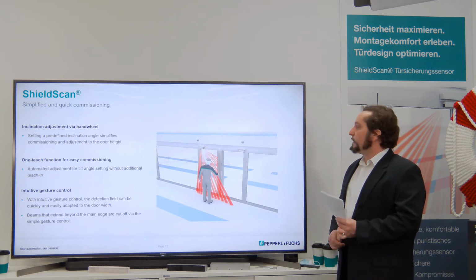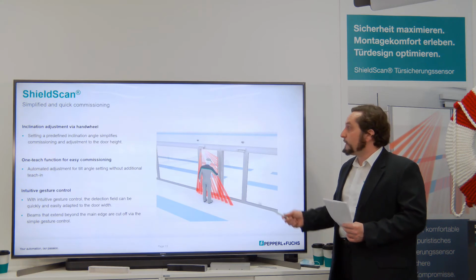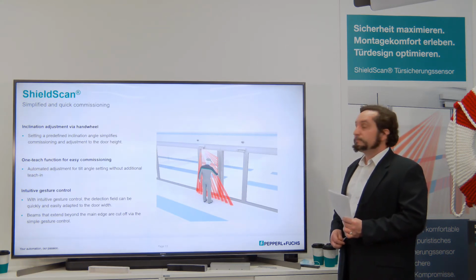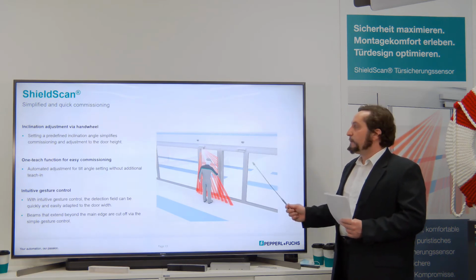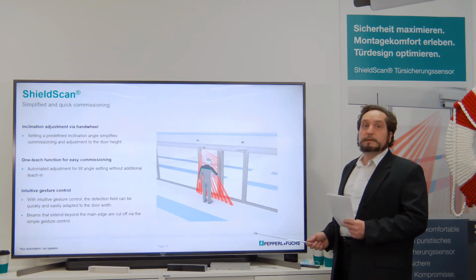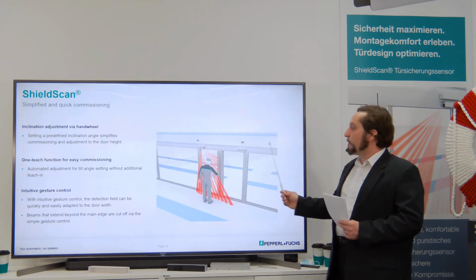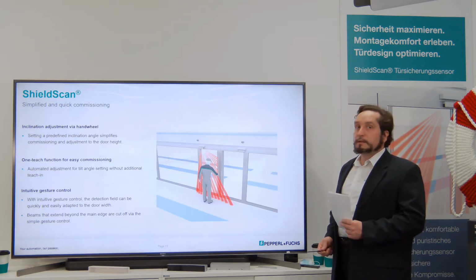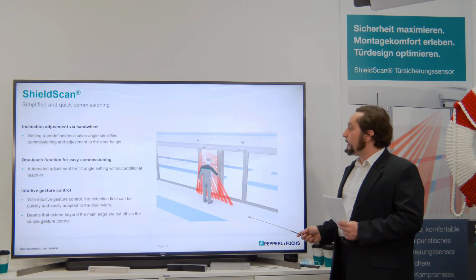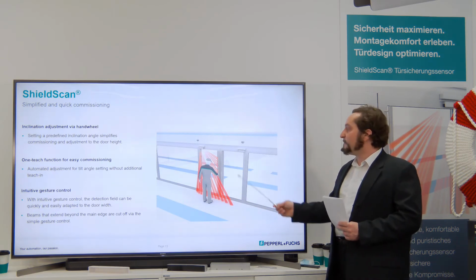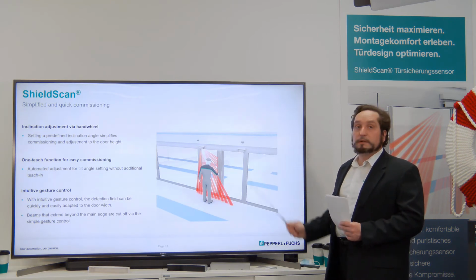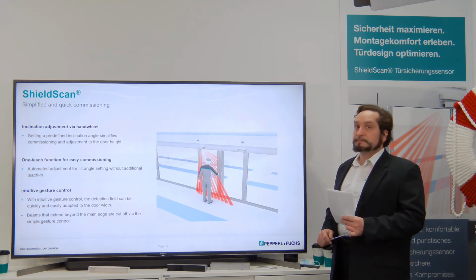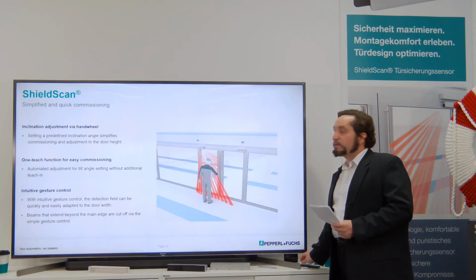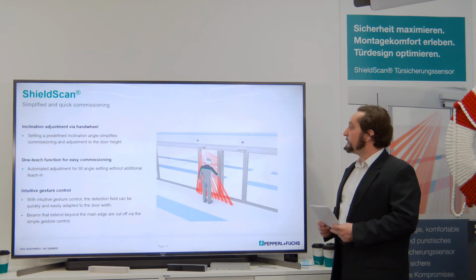We have to install and do the settings on the sensor, then start the commissioning procedure. We adjust the setting dial and set the dip switches for the height and width of the door. It's very easy to teach in - we don't need another control or a remote controller, for example. It's just enough to do a gesture control by teaching in with a simple hand movement, vertical along the main edge. This is how we teach in the width of the door during the commissioning of the sensor.